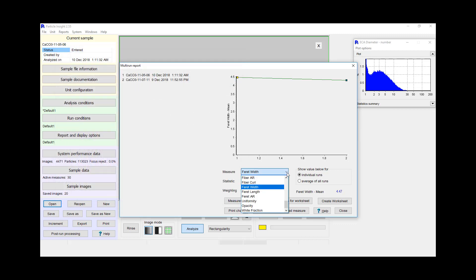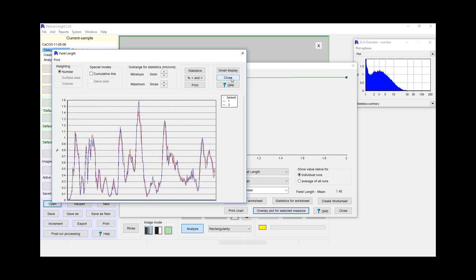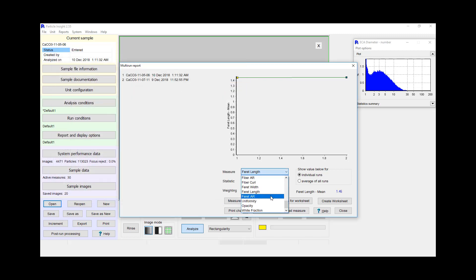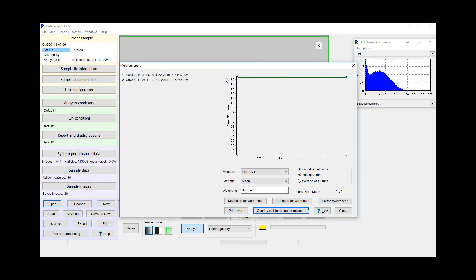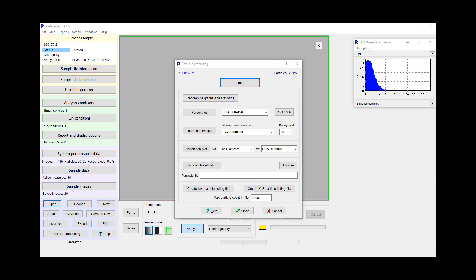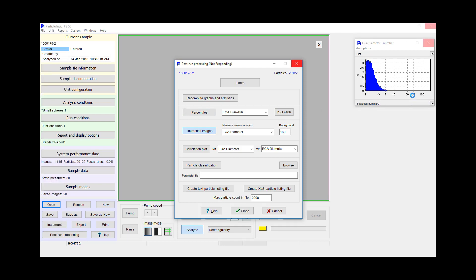So quite a large number of different measurements that we can take to look at differences in shape, not just size — width measurements, length measurements, and the aspect ratios correspond as well. Very interesting. I have some other samples for calcium carbonate. Here we have another calcium carbonate — I believe this sample is precipitated and it is very small. I believe this one is being used for the paper industry. Let's look at some of the thumbnail images. We're looking at a number distribution — pretty small particles between one and two microns.